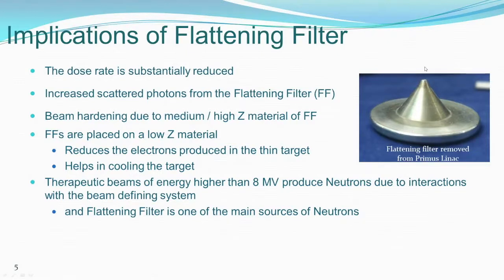The X-ray beam, which is a Bremsstrahlung beam and polychromatic, when it passes through this, has its soft components cut off and the beam is hardened. So you have beam hardening because of the high Z material. It is also placed on a low Z material, which reduces the electrons produced in the thin target and helps cool the target. The therapeutic beams we normally use are about 10 MV or 15 MV. Anything more than 8 MV would produce neutrons due to photonuclear interactions with the material in the path of the beam, and the flattening filter is one of the main sources of neutrons from a linear accelerator.